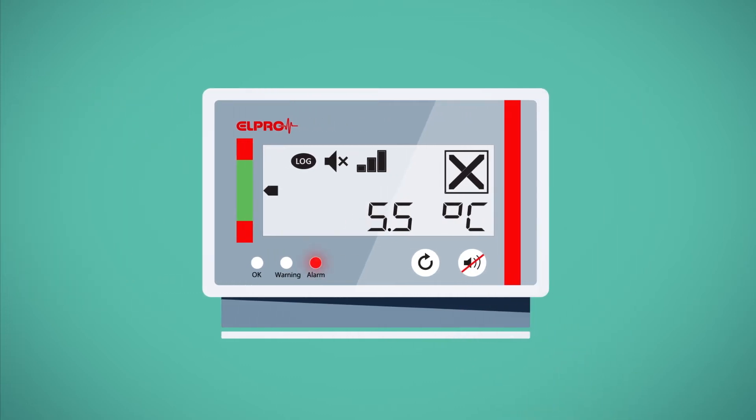Press the mark button repeatedly to scroll through the following information on the display: set mark, today's date, the current time, highest temperature, total time above limit, lowest temperature, and total time below limit.